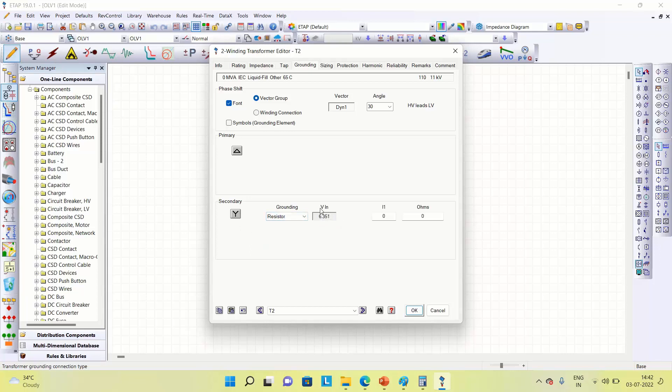Let's go to grounding: delta star, resistor grounding. You can see 6.351 kV, this is the phase voltage. We want to restrict the current to 400. The corresponding NGR required is 15.877 ohms.